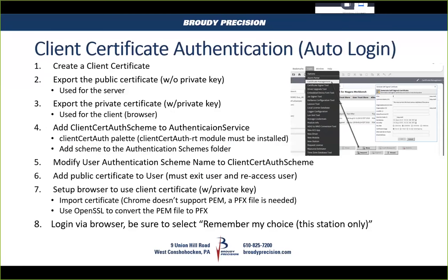And then different browsers do it different ways and require different formats. I put down the basic procedure for doing it, and for using Chrome. The standard certificates that Niagara uses are PEM file extensions, and Chrome uses PFX.